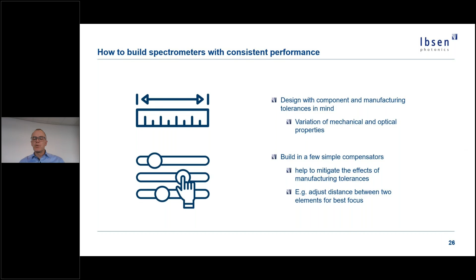To reduce the downtime of these instruments in daily use, we want the spectrometer to be calibration free. The calibration basically gives the relation between a pixel position and a wavelength on the detector. This calibration is done at the factory at the time when the spectrometer is being manufactured. If the parts inside the spectrometer shift position over time, there is a risk that the spectrum permanently changes position on the detector and therefore needs to be recalibrated.